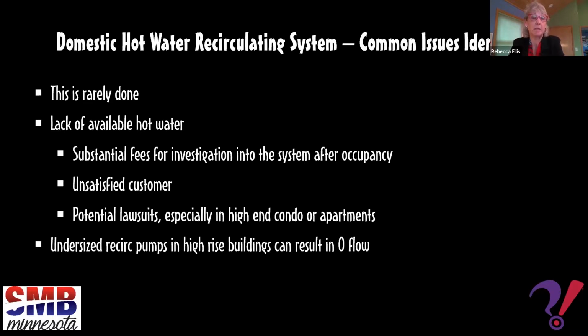The domestic systems are called open systems, and it's a different pumping strategy or design that you have to think about. You not only have to pump through the pipe, which creates friction loss and pressure drop, you oftentimes have to pump it to the tops of a tall building. And if you don't account for all that hydrostatic pressure in that column of water as you're trying to push the water back up to the top of the building, it's just not going to flow.